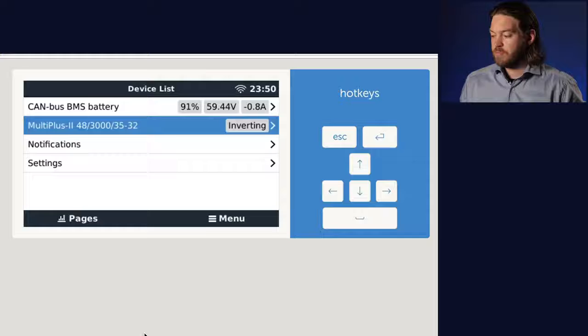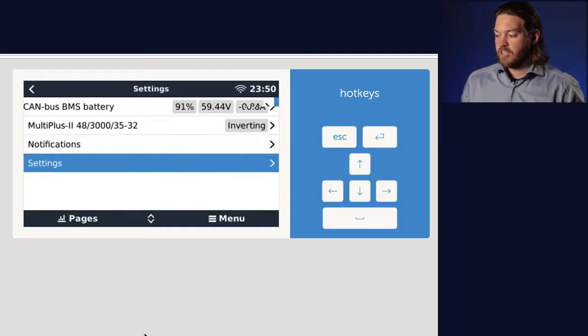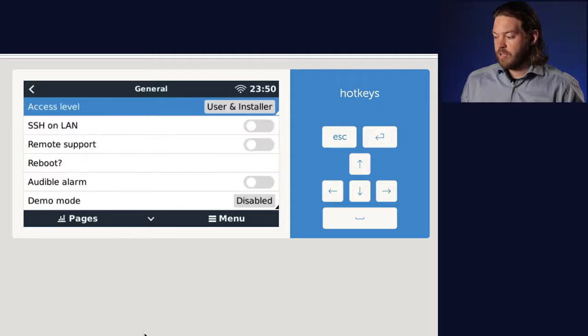If you have any issues connecting the GX device to this 3-phase system, especially to begin with, it can help to have all the 3 units turned on first before they're connected to the GX device. You can then connect the GX device and it should find the 3 multis. If it doesn't, you can reboot the GX device through its menus. This is found in the Settings, General and Reboot.